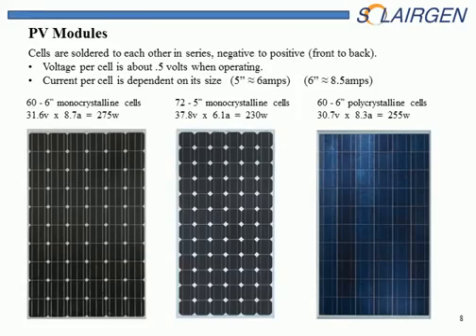The other component is amperage. Each cell, depending on its size and the intensity of light, will produce somewhere between 1 amp up to maybe 10 amps. These are tested at standard test conditions, with a radiance that's consistent and a temperature that's consistent. So when it varies from those temperatures or radiance, it is different. What you're seeing here, the 31.6 volts and the 8.7 amps, is based on a controlled light intensity and temperature. It's also dependent on the actual size of the PV cell. So we have 6-inch cells, we have 5-inch cells, and we have other different dimensions as well. So the amperage will depend on that actual dimension. The wattage of the PV module is, of course, the product of volts times amps.